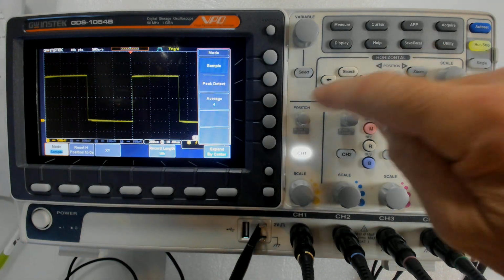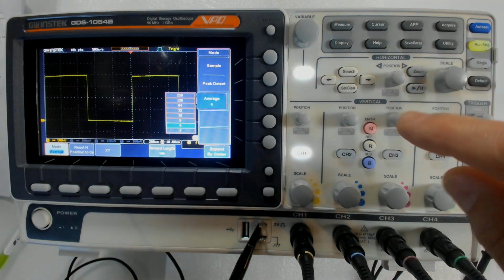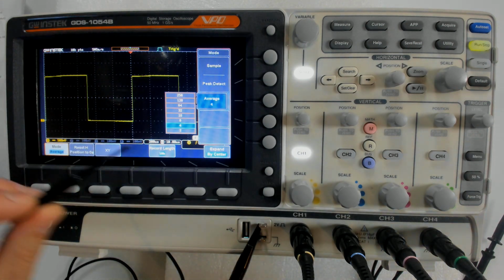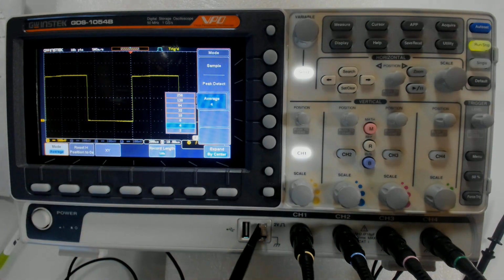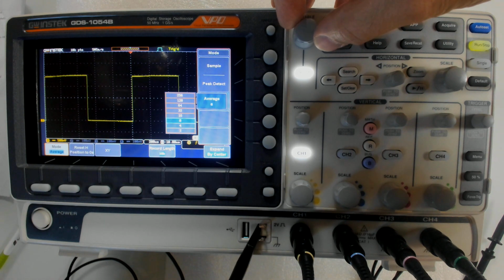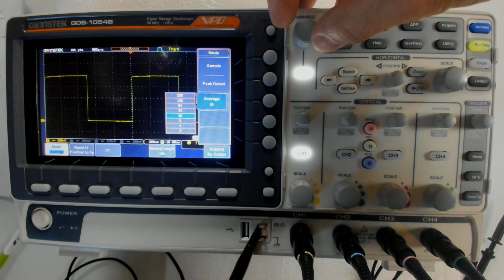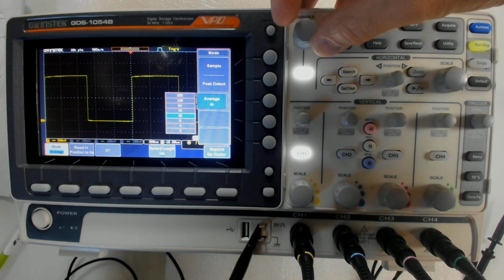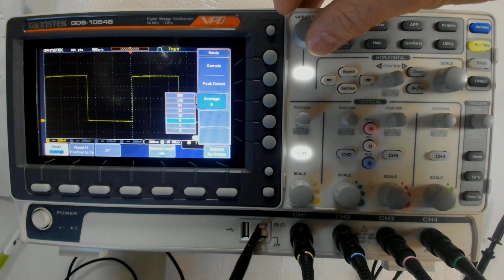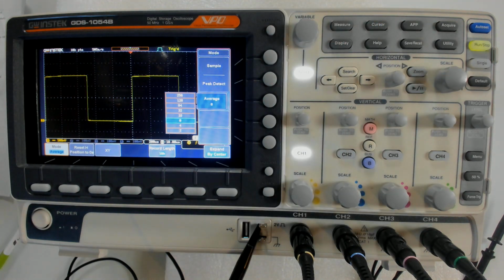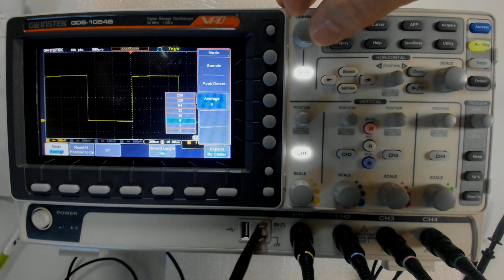Okay, so let's go ahead and try the averaging. Right now, you see how it cleaned it up a bit? It's taking 4 samples and averaging them together. If I increase the number of averages, it might even get more of a pencil line. At some point, you're averaging and it doesn't really make too much difference. But maybe 16 or 8. It does slow down the acquisition though, so you always have to remember you're going to now take 8 readings and then display it.